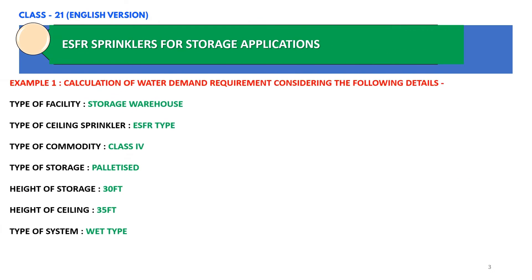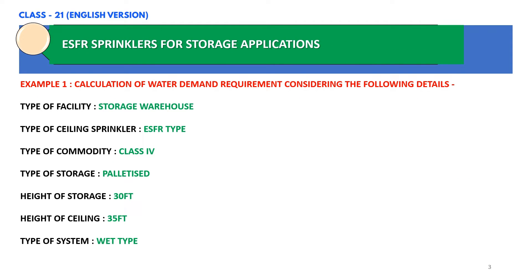Let us consider an example in order to calculate the water demand requirement using ESFR sprinklers. We are going to consider a storage warehouse where the type of ceiling sprinkler will be ESFR type. Commodity classification is Class 4, type of storage is palletized, height of storage is 30 feet, height of ceiling is 35 feet, and the type of system is a wet type system.